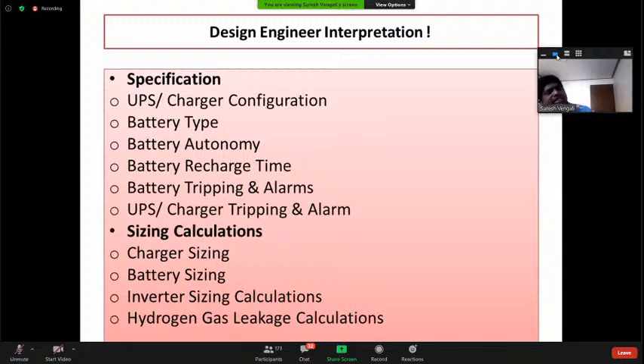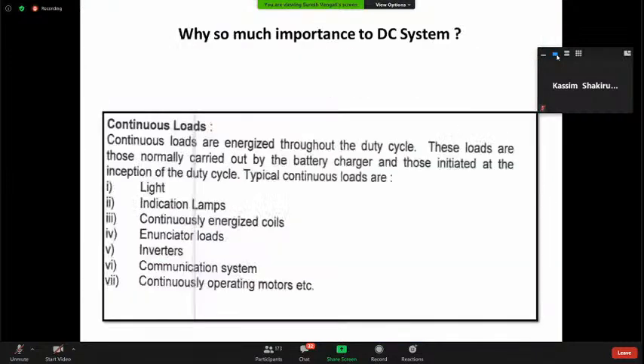Next is battery autonomy. To decide battery autonomy, you first need to understand battery sizing, and for battery sizing you need to check your loads. This is a different topic with different sizing criteria - you can find many battery sizing criteria online, particularly IEEE 485 and another IEEE standard that defines how to size a battery.